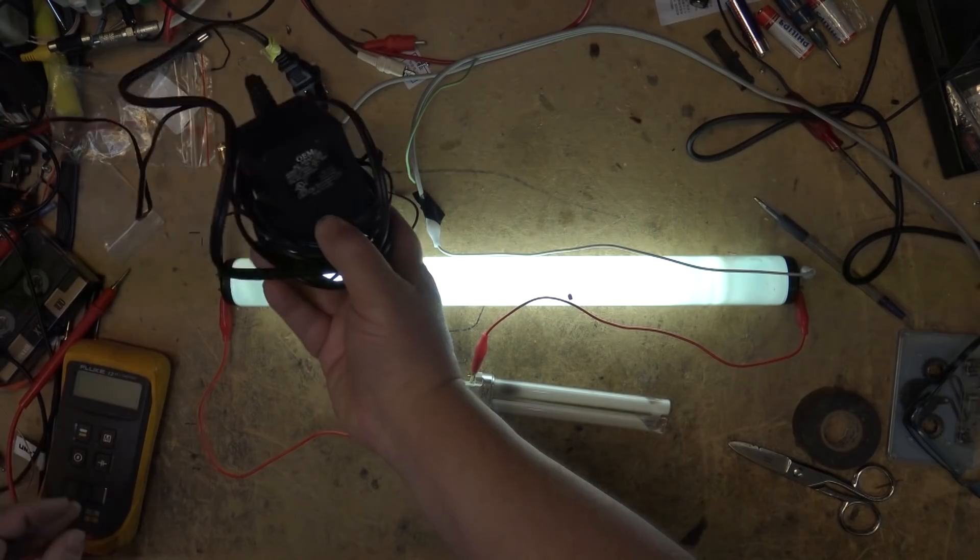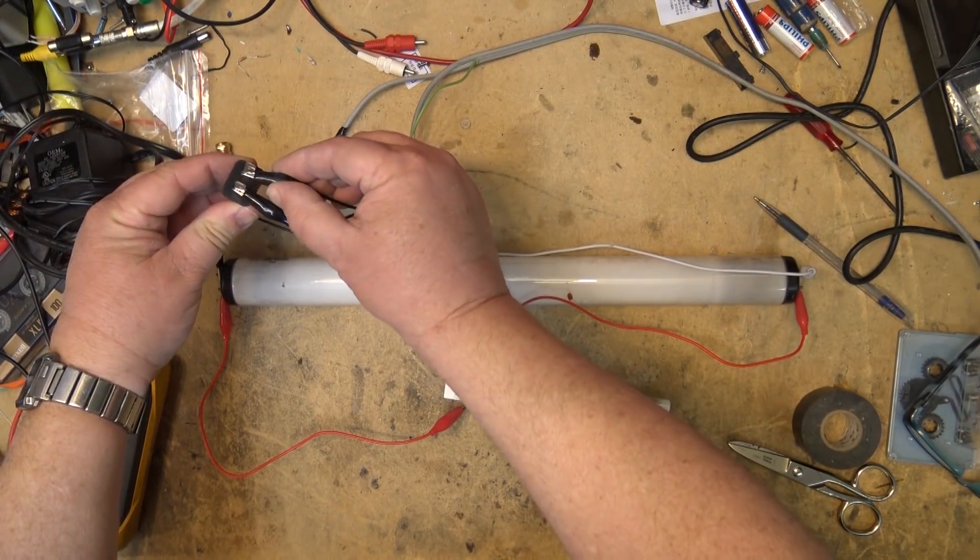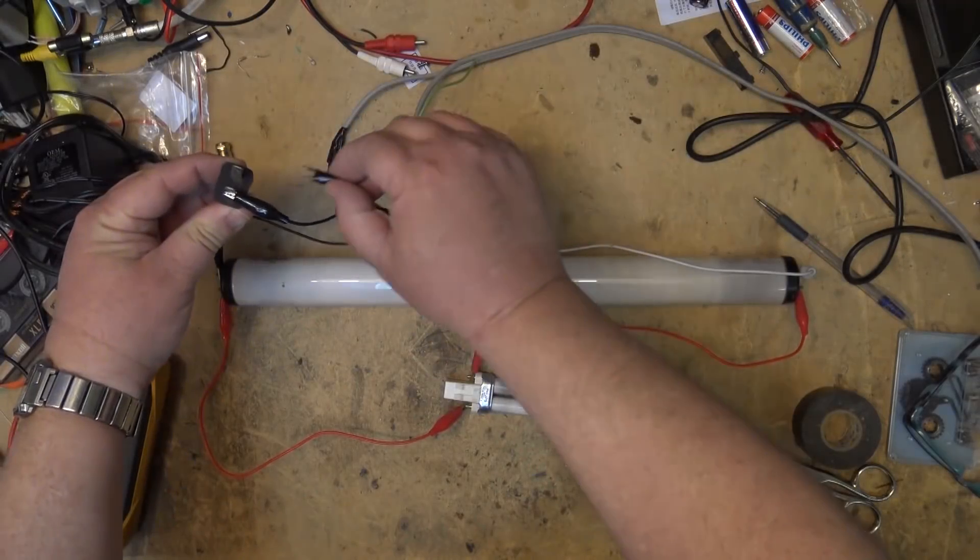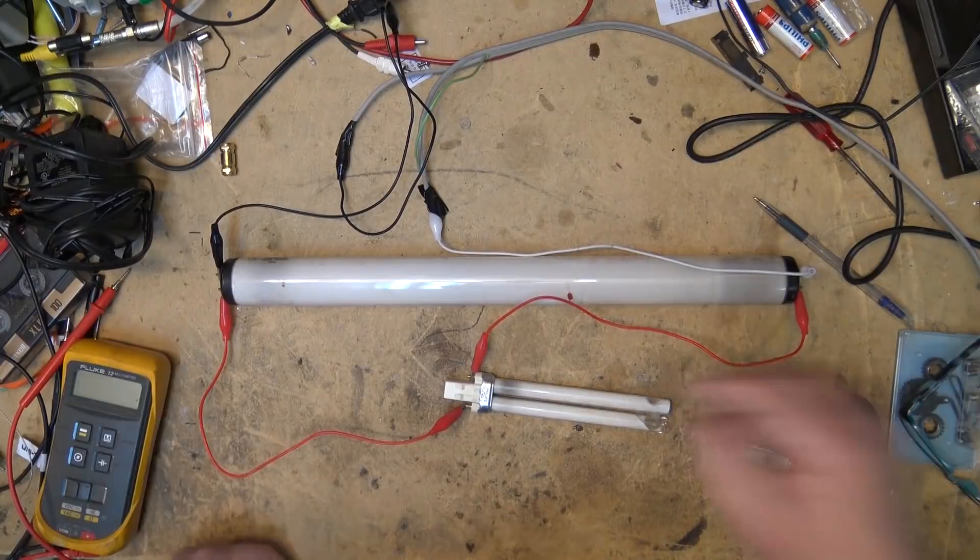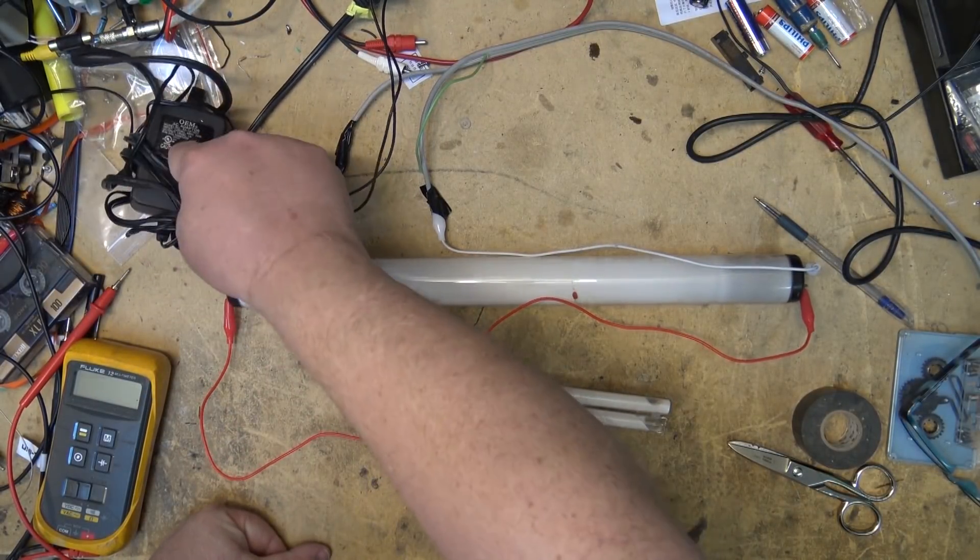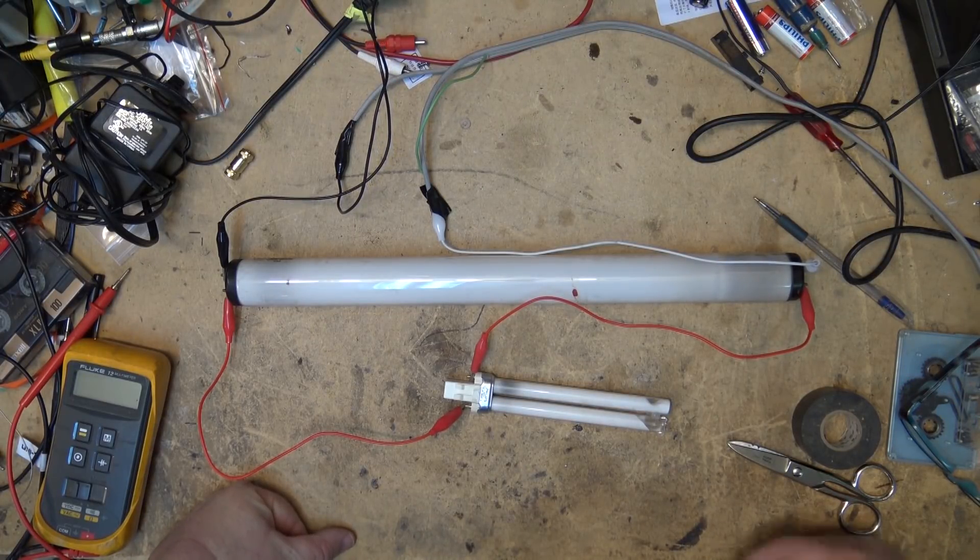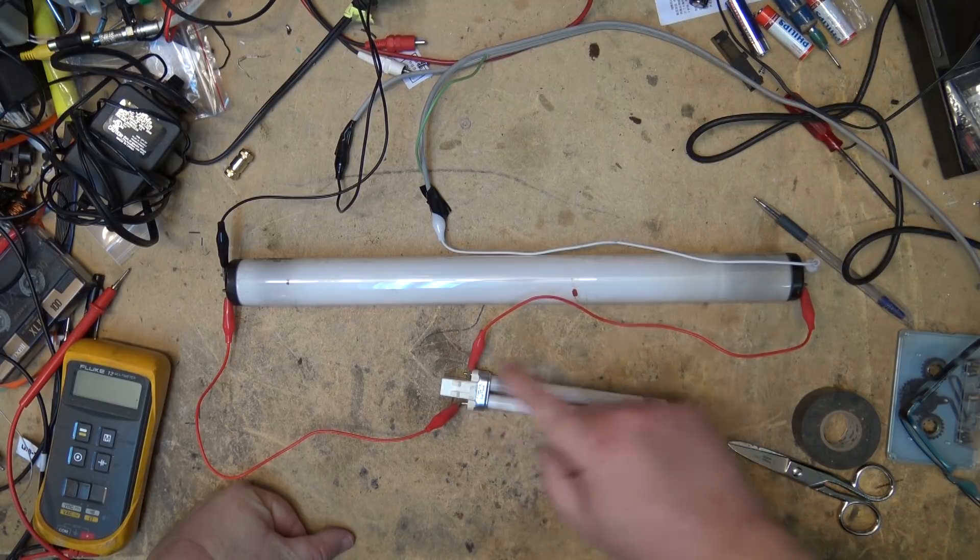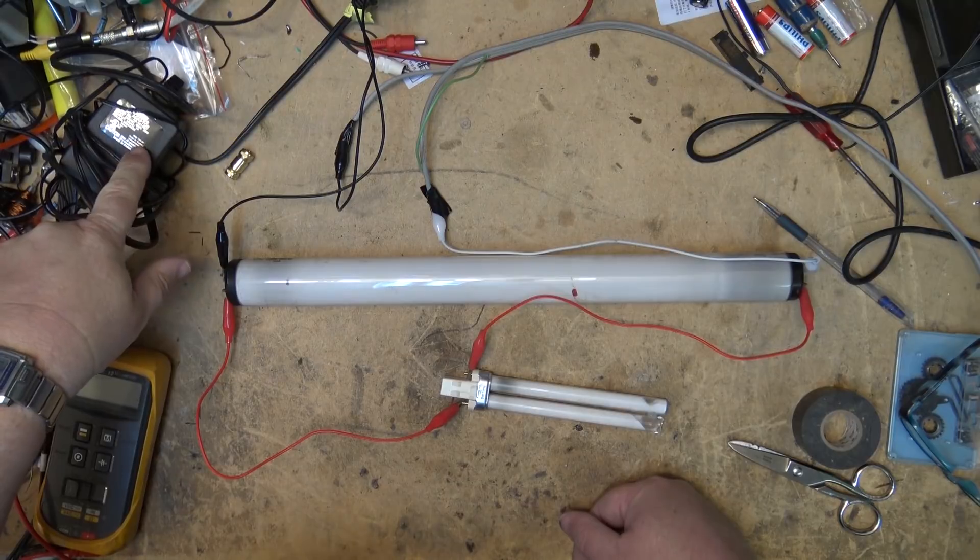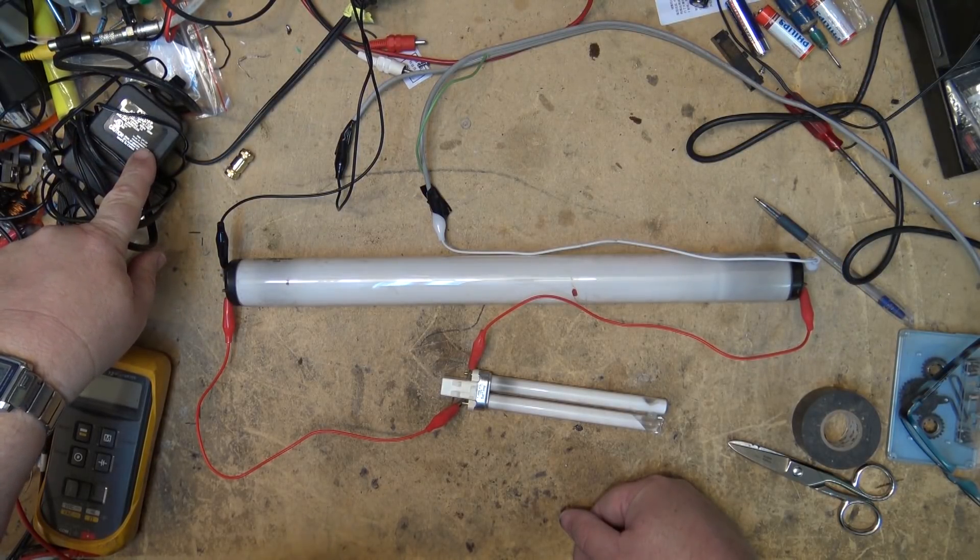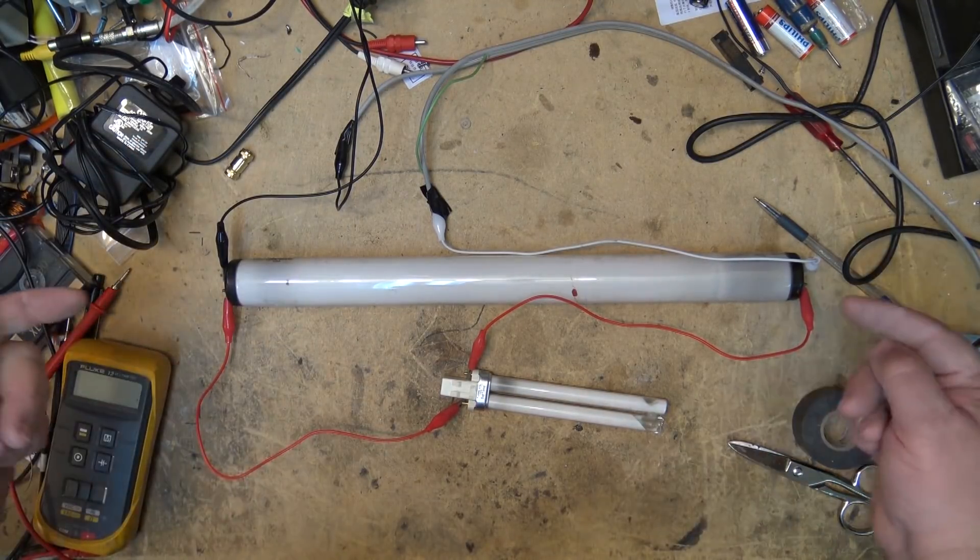Now, what is happening here is the primary core or the primary winding in here is just acting like a big choke coil. What happens is when the switch closes here, it heats the filaments up in the end of the lamp. It also builds up a magnetic field in the primary of the transformer. And then when the switch opens, that magnetic field collapses and it gives you a kick.